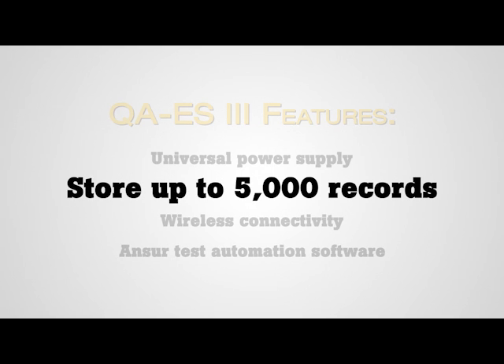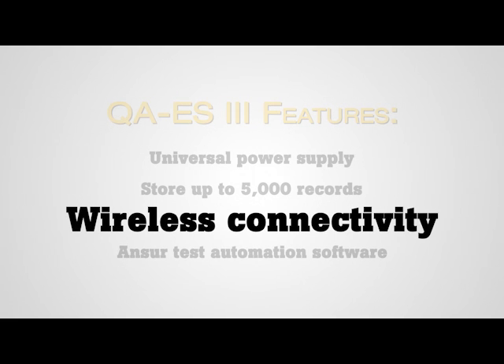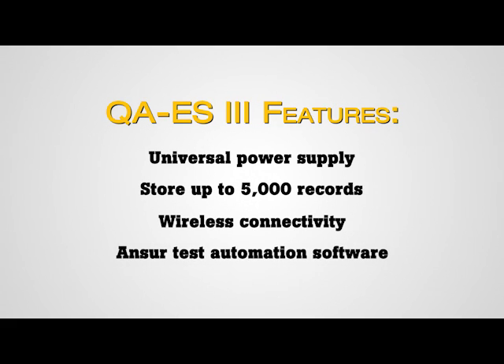Also contributing to the QAES-3's reduced test times is its Bluetooth wireless capabilities, which makes it possible to quickly and conveniently transfer results to a PC. The addition of Ansur software further automates and standardizes testing, speeding up overall test times and minimizing human error.